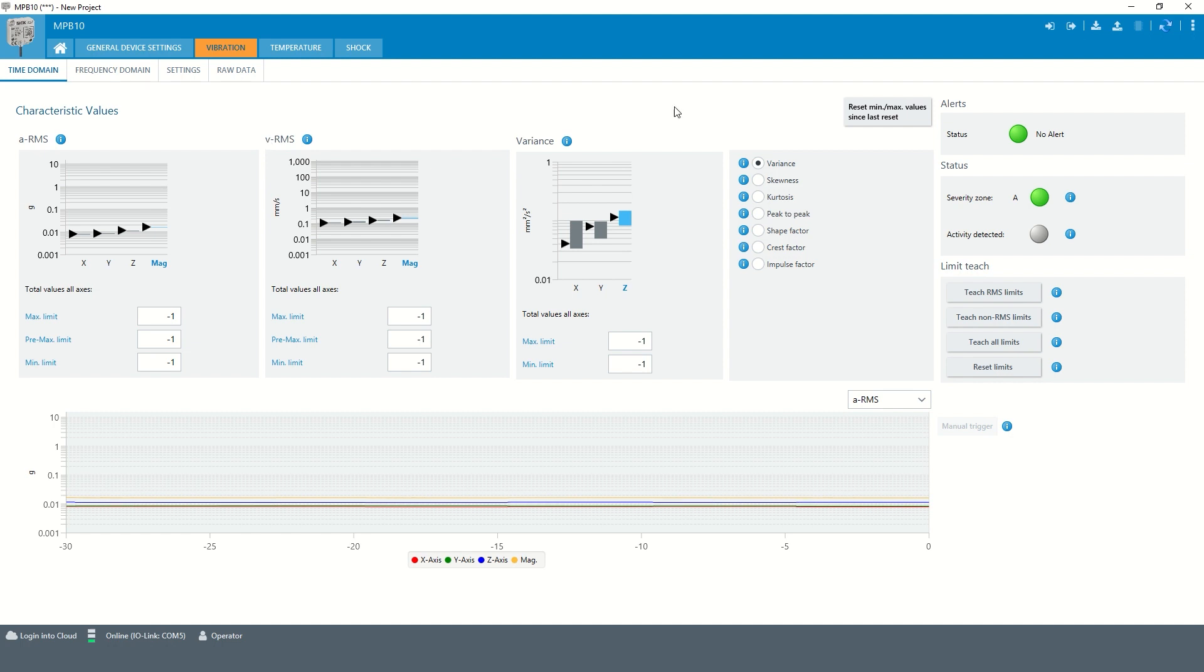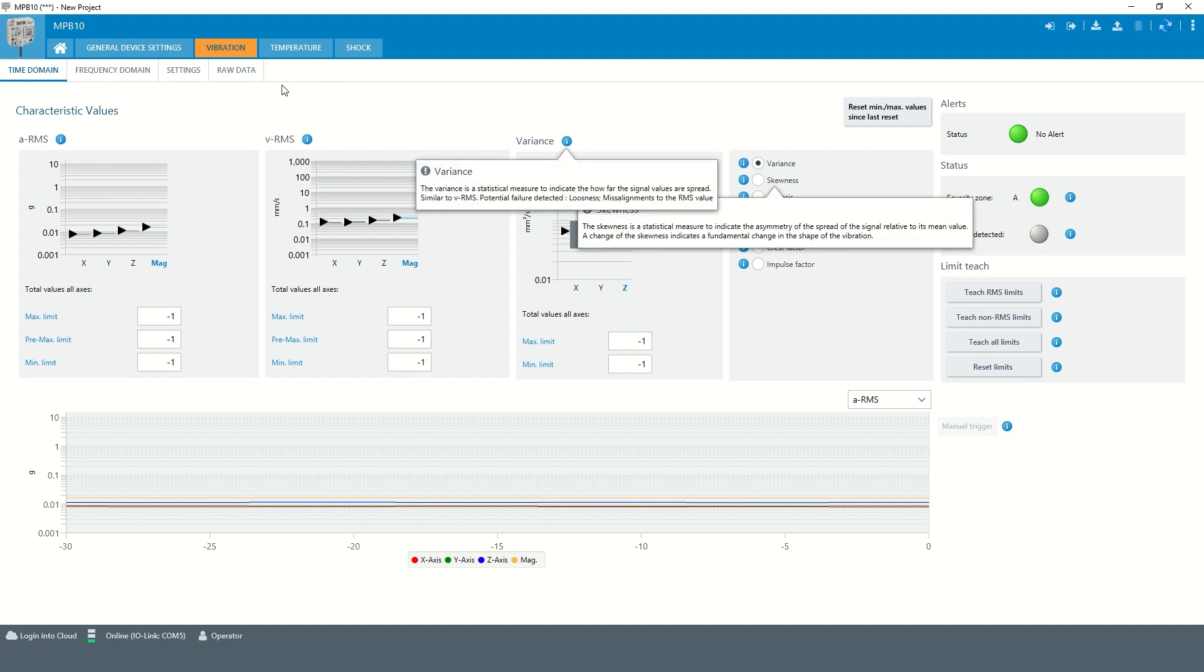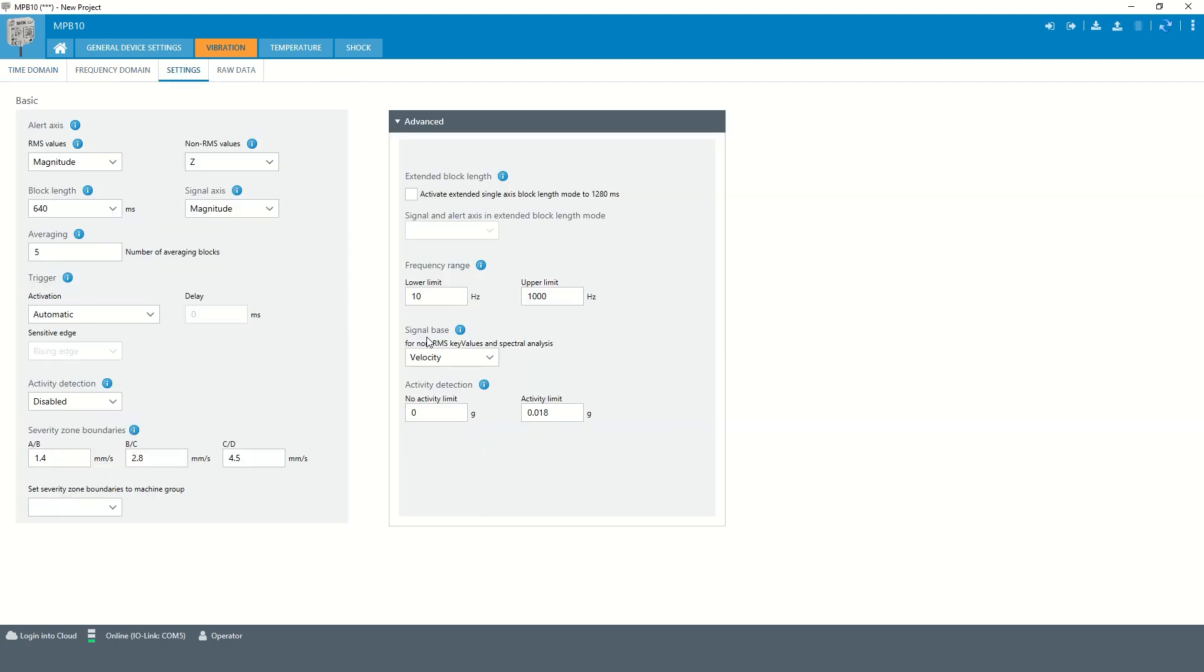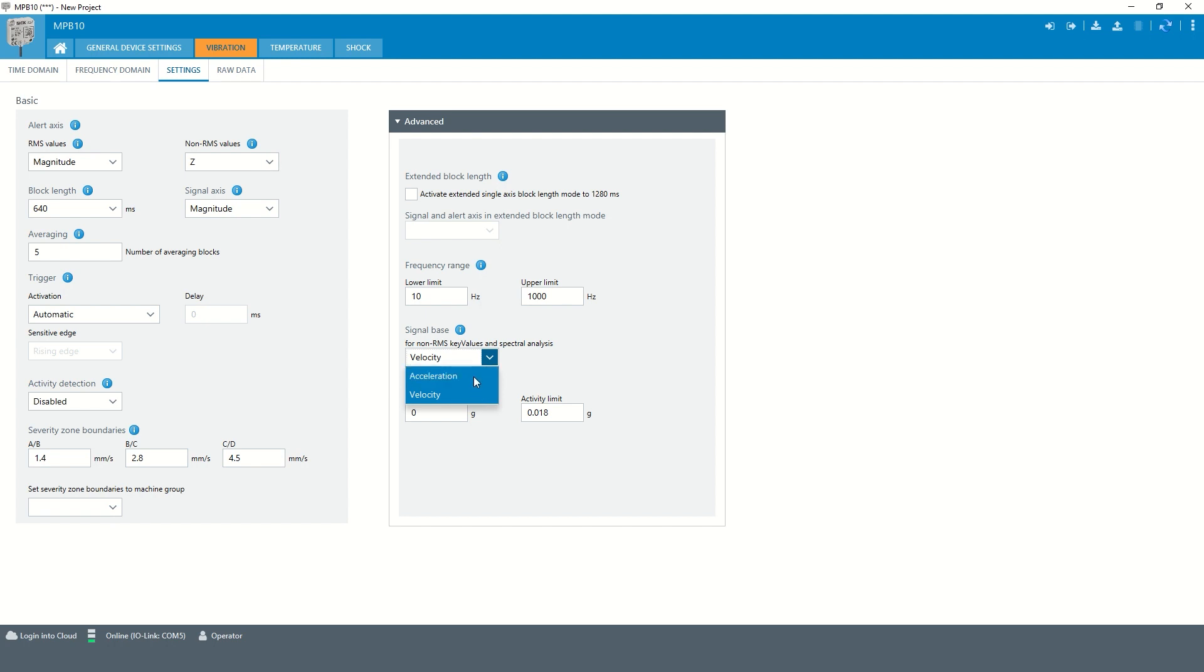For all other time domain key values, the signal base, acceleration or velocity, can be selected in the advanced settings. Please be aware, this selection is valid for time domain and frequency domain. Phenomena that primarily cause vibration at frequencies up to 1000 Hz can be better observed with velocity-based vibration values. Acceleration based key values should be used to detect phenomena that primarily cause higher frequency vibrations.